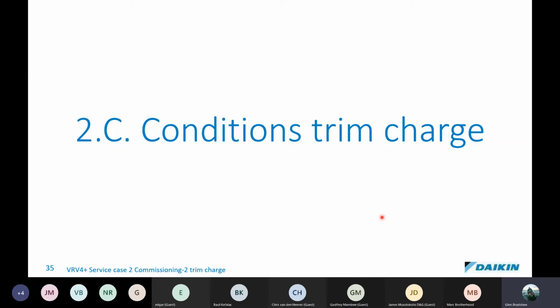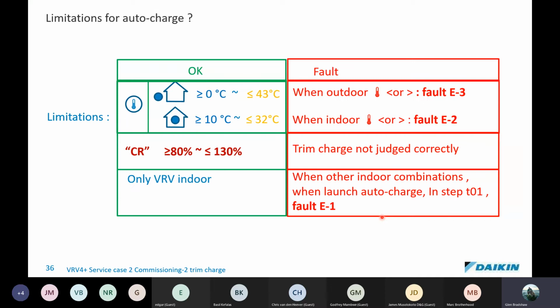Now, obviously, these trim charges cannot be done under all conditions, so we need to know what conditions are required in order for them to happen. The outdoor conditions must be greater than 0 degrees Celsius and less than or equal to 43 degrees Celsius. When the outdoor conditions are outside of these parameters, you may get a fault E3.